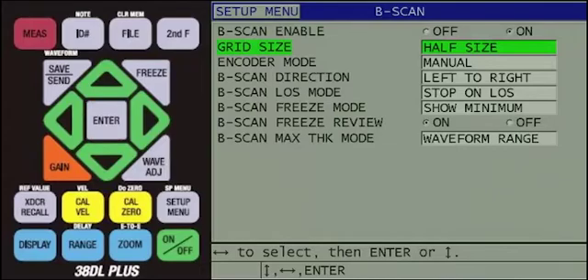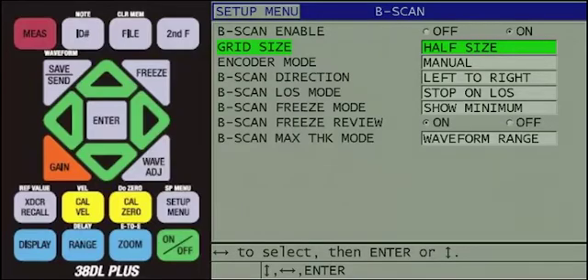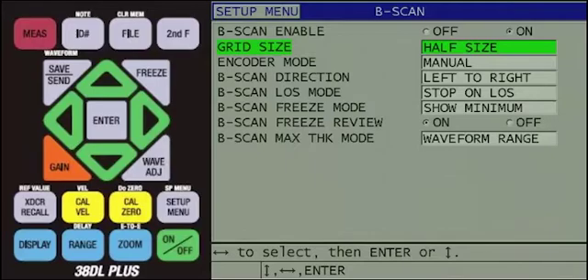For grid size, you have the option to display the B-Scan as half size or full size, which was discussed in previous slides. Typically, we recommend half size, so you can still see the A-Scan while you are scanning. This allows the user to easily observe if they are making a valid measurement or if the gauge is measuring a signal from noise.